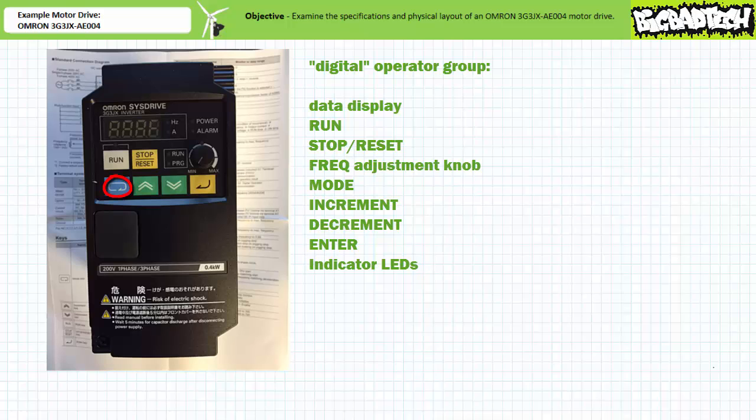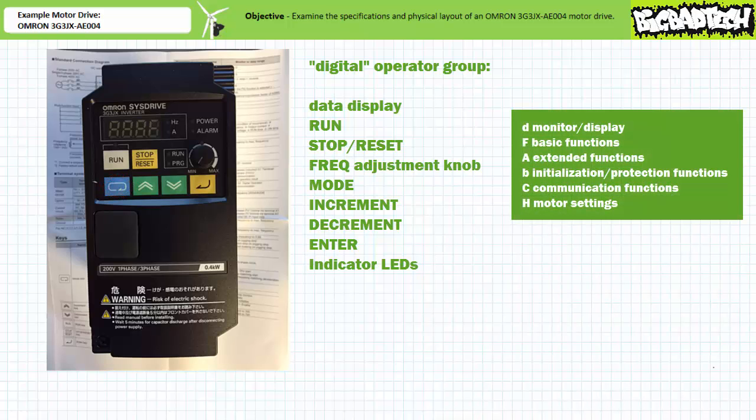The mode button switches between different functions: monitor or display functions preceded by a D, basic functions preceded by an F, extended functions preceded by an A, initialization and protection functions preceded by a B, communication functions preceded by a C, and motor settings preceded by an H. We'll come back to explain various elements of these different modes when we learn to program this motor drive.